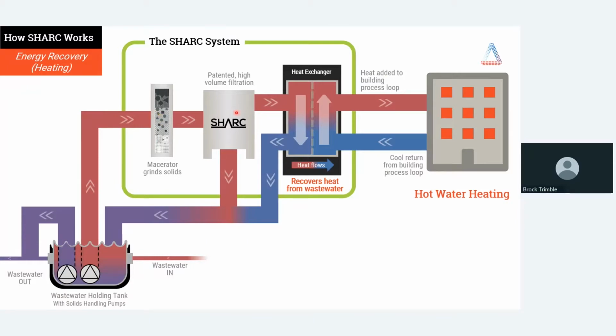The SHARC will filter those solids, extract them out the bottom, and send them back to that wastewater source. And all of that filtered wastewater then passes through the heat exchanger where it moves its energy to or from your building. So in this case, we're looking at energy recovery. The energy from the wastewater is absorbed into the building loop, where that energy will then be taken into your building to be used again as a source for domestic hot water, hydronic heating, really any type of hot water application that you might be able to think of. And then as that wastewater temperature is lowered, the stream simply returns back to the wastewater source or right down to the sanitary sewer and discharges. So we're really only interested in collecting and capturing all of that energy, putting it back into the system that it came from, and ultimately getting rid of the wastewater down into the systems that it would normally flow to.